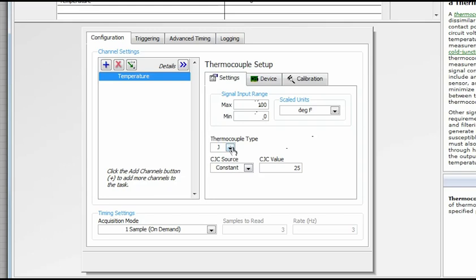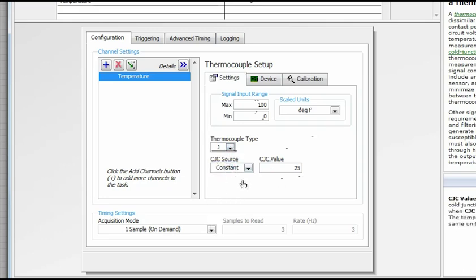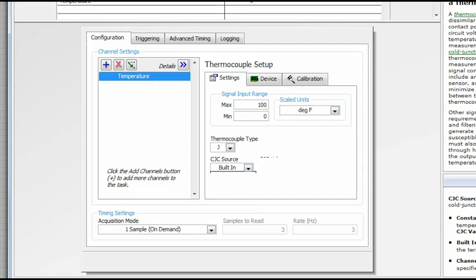We can set the thermocouple type. In this case, we're using a J-type thermocouple. And as we said, the module has built-in cold junction compensation, so we can change that to built-in. And that's all we have to do. We'll hit OK.